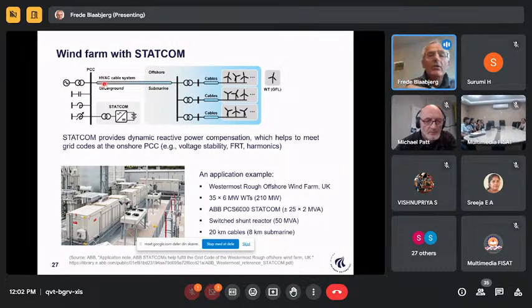In that context, there is also an evolution in power electronics by doing what we call a STATCOM, which is able to deliver reactive power, as well as help with other critical situations, for example low voltage ride-through, and also compensate for harmonics.